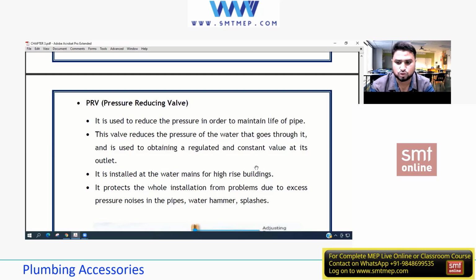The reason to install it here is that there will be no excess pressure. The UPC and IPC codes set the standard value because they sense that if the pressure does not increase more than 60 and 80 psi at that particular height, in those particular floors, that is sufficient, and there is no excess pressure that will damage the fixtures. Getting my point? Yes or no? Yes, sir. Right. So that's the reason we are cutting down the pressure which might cause a problem in future to the fixtures.